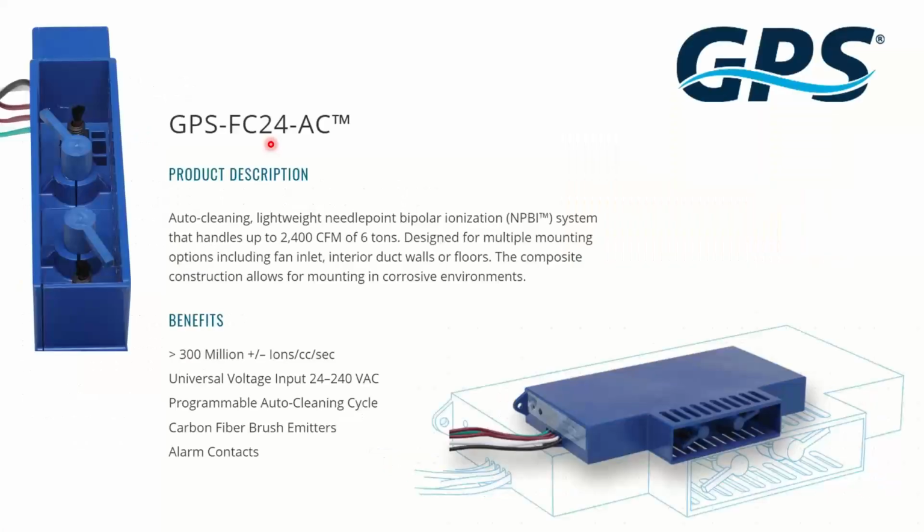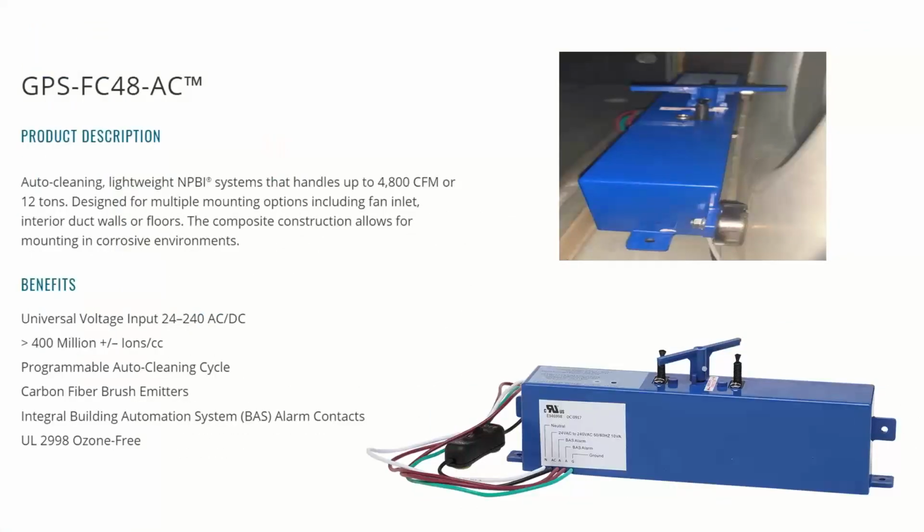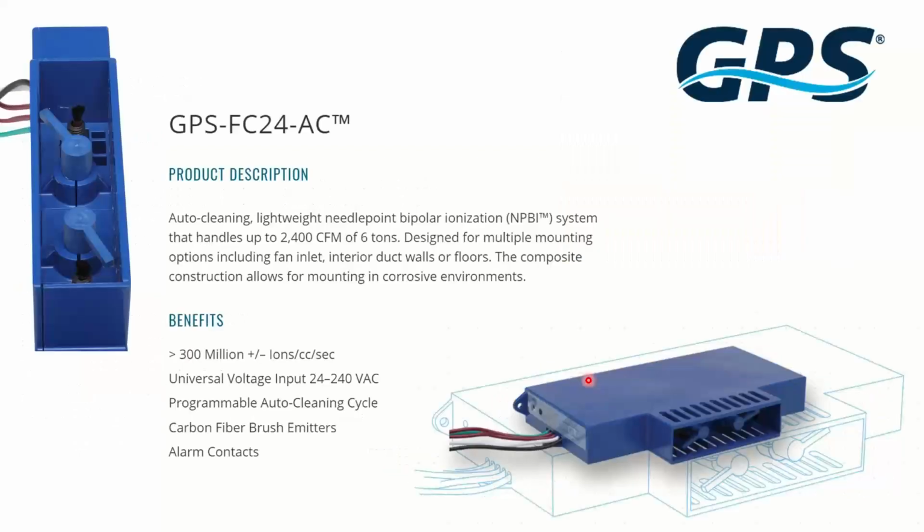They're very similar. They both mount on the unit. They can be mounted by screwing it in or a magnet, either way. These large magnets go on here. And then they both have a way of keeping the needles clean. This one's got this little windshield wiper, bipolar, so two sets of needles. These are needle point, so I have all these little carbon needles on here. And then once a day, this wiper goes swish, swish, and knocks any debris off it.